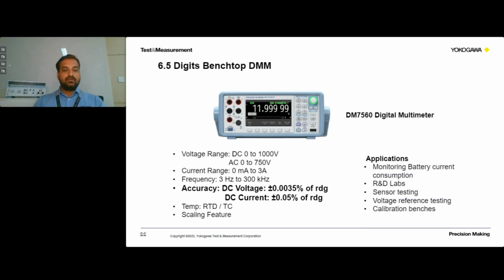That means we will be able to measure higher values of voltage and current through CTs and PTs. And a couple of applications where this benchtop DMM can be used are monitoring of battery current. As you can see here, the current range for this 6.5 digit multimeter is up to 3 amps. So for monitoring of the battery current, that means to measure the very minimum current, this can be used. And R&D labs, where checking and testing of the very minimum current in the lower ranges is very crucial, it can be used there. Sensor testing, it can be used, and voltage reference testing. That means if you are designing a voltage source, the voltage source will have voltage references which generate voltages inside the unit. So it is very critical to check how effective or how accurate the voltage references designed for those kinds of sources are. So that kind of voltage reference testing can be done using this multimeter, and this can be a product for your calibration bench also.